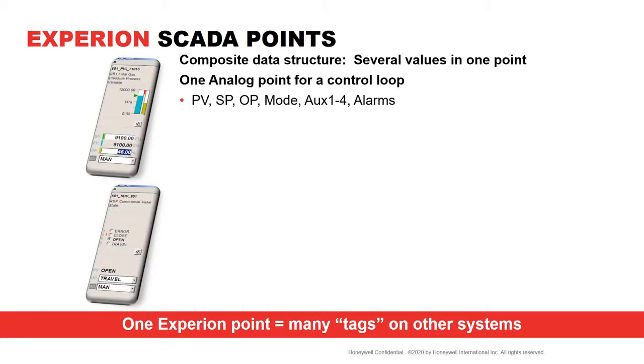Now moving on to talk about Experion's point structure, it is an important topic when we start to talk about scalability and sizing, as Experion points have a composite data structure. They represent several field values in a single point. For example, for an analog control loop, the process variable, the set point, the output, the mode, and all related alarms and other parameters are components of a single SCADA point.